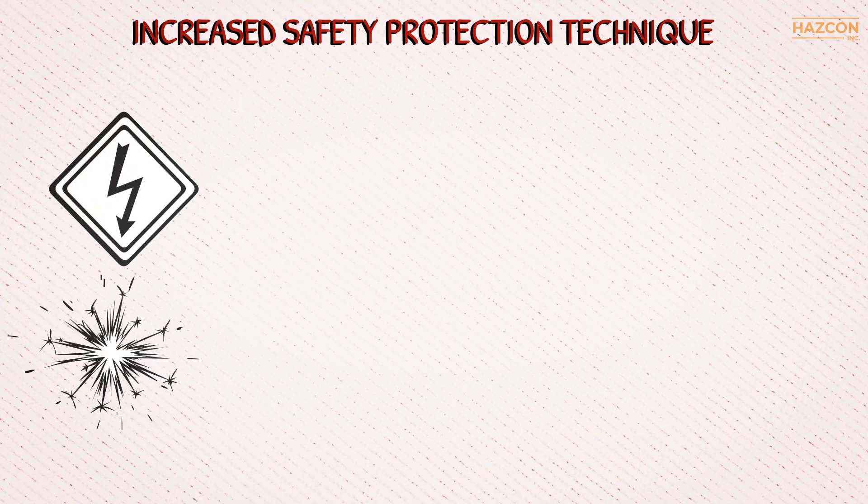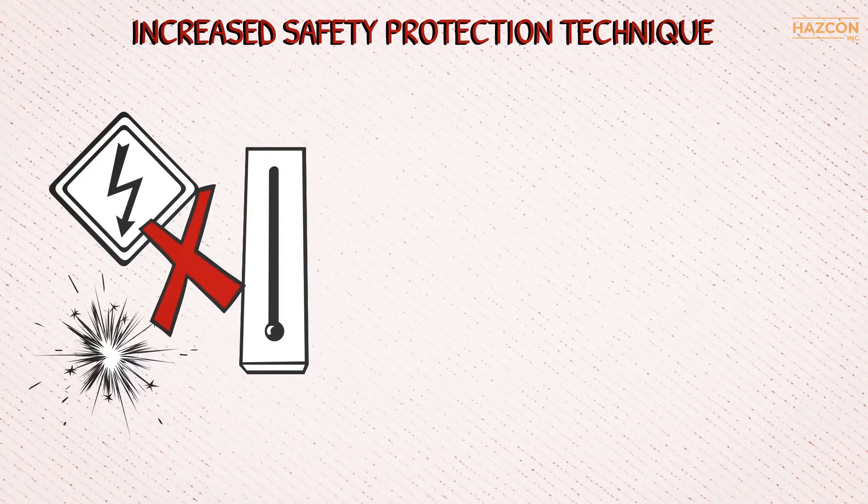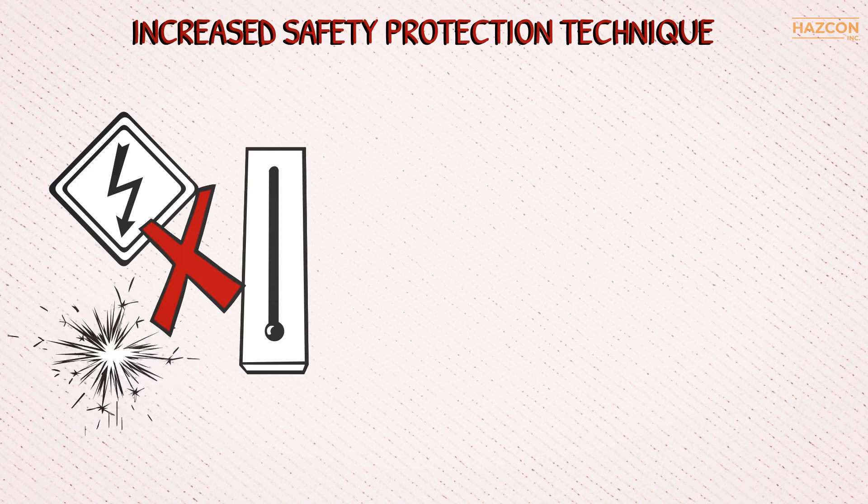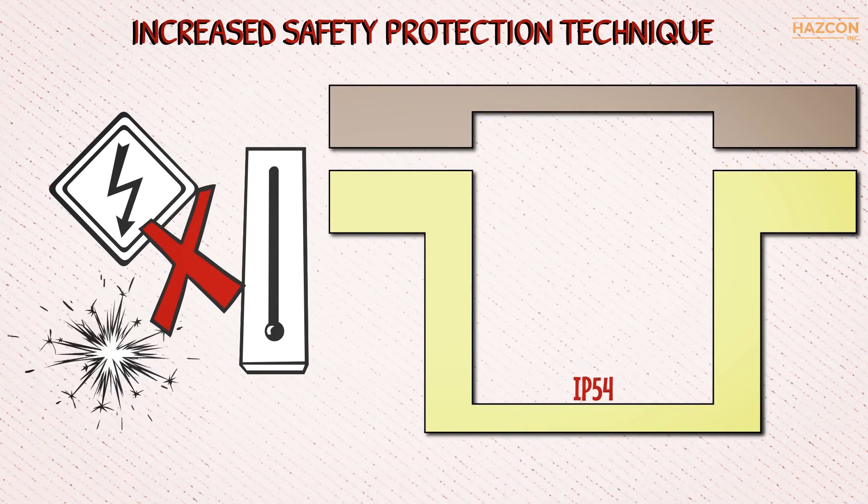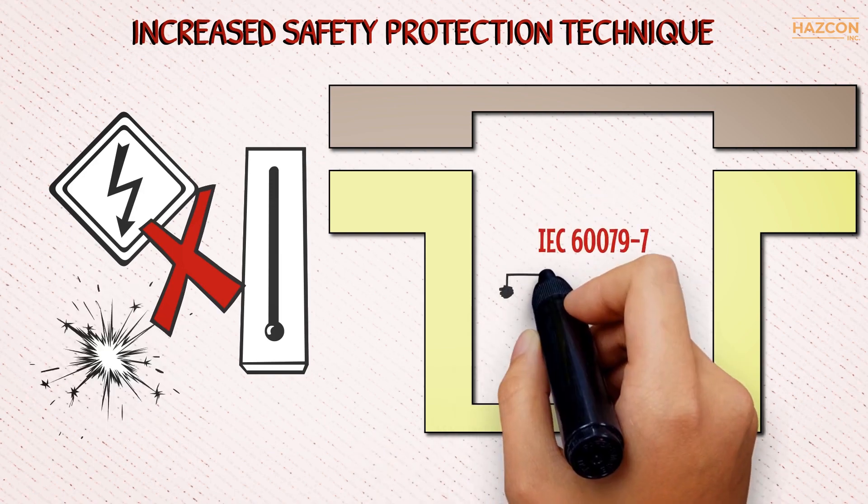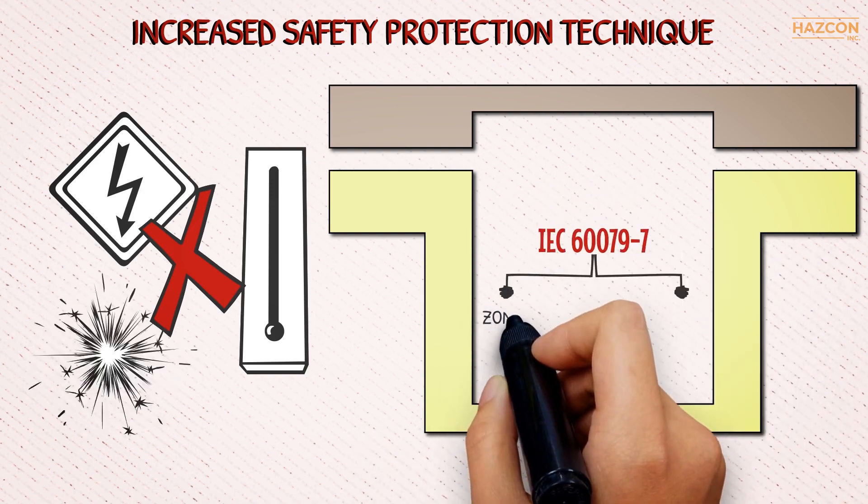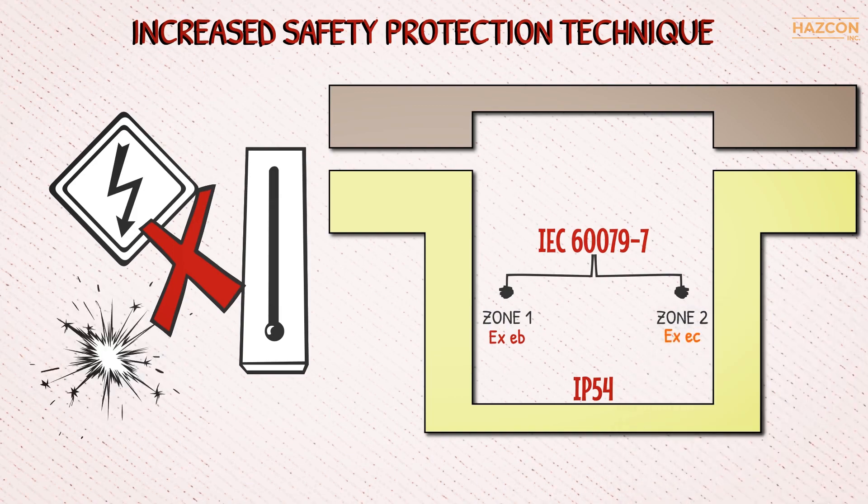In summary, the increased safety protection technique relies on the fact that no arcs, sparks, or hot surfaces can be present under normal conditions for Ex ec and under fault conditions for Ex eb. There must be an enclosure which must be able to provide IP54 protection for internal components. Products must comply with IEC 60079-7 in order to use the increased safety protection technique for Zone 1 and 2.